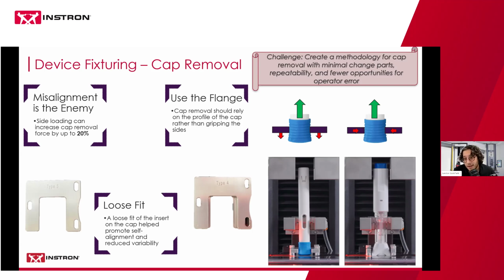For that reason, a lot of customers do testing differently. The biggest thing we learned immediately was that any misalignment in the system has a major impact on the cap removal forces. So if you have side loading, any error in concentricity or angularity, we saw the cap removal force could artificially increase by 20%. So we knew alignment was going to be part of our solution.